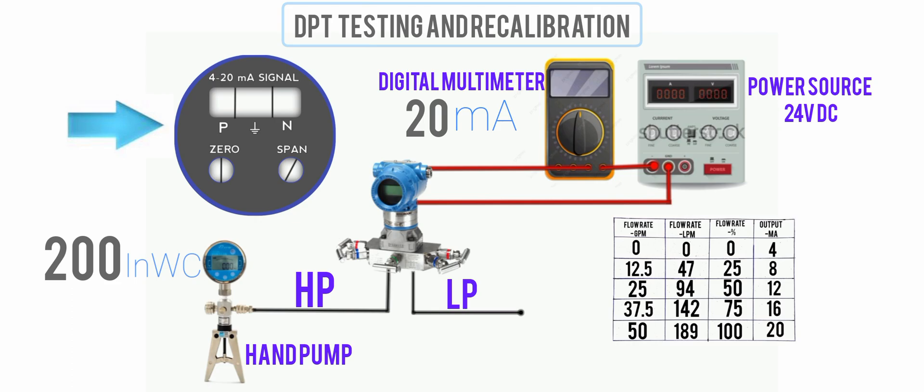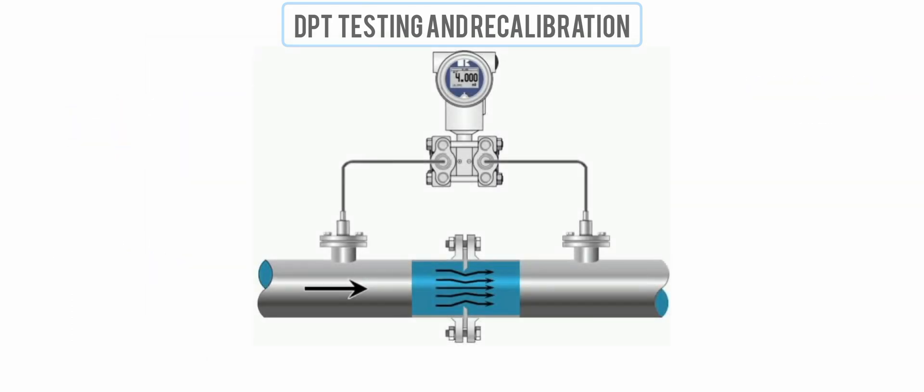Now that you've recalibrated, it's a good idea to apply all of the values from the calibration table and record the corresponding output current values. Let's return the transmitter to service now that it's been calibrated.